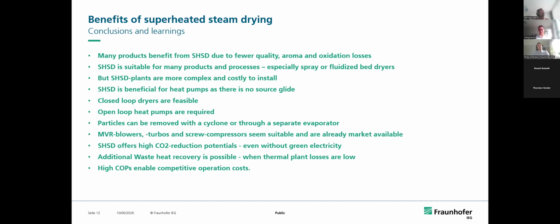Superheated steam drying processes don't have a glide on the source side. This is valuable for heat pump integration, and the drying medium, steam, is also operated as a refrigerant, making it even more efficient. Open loop heat pumps are required, and if you have concerns about dirt, you can use a cyclone, or change to a closed loop system while maintaining the same blower or screw architecture.